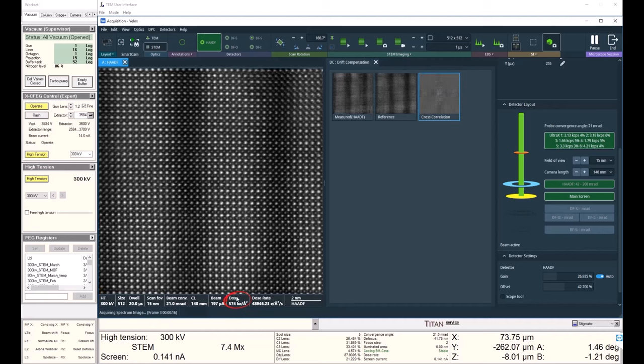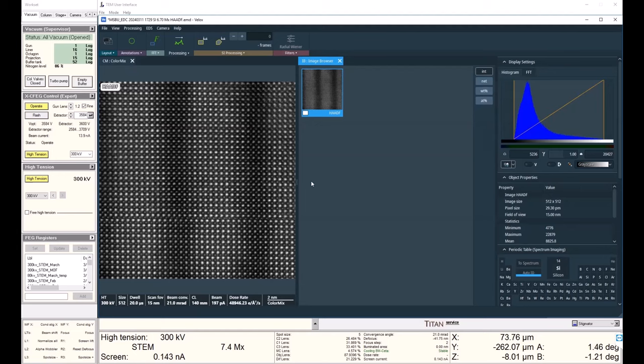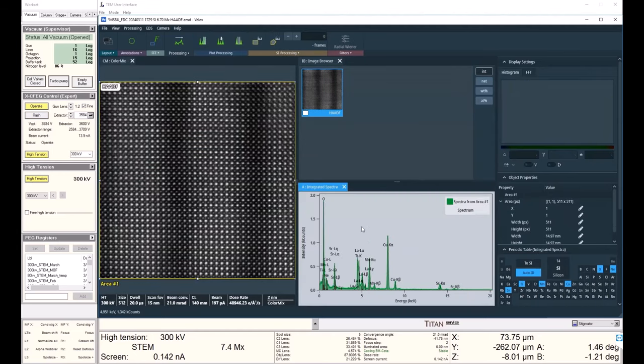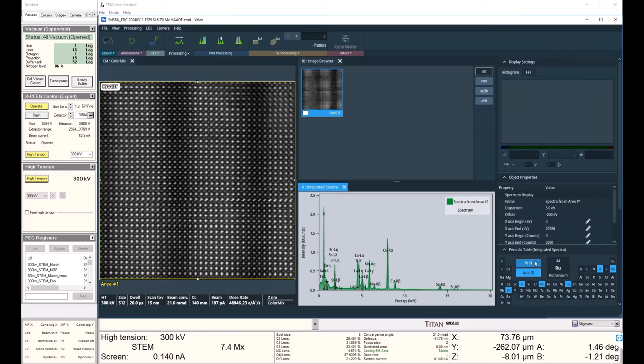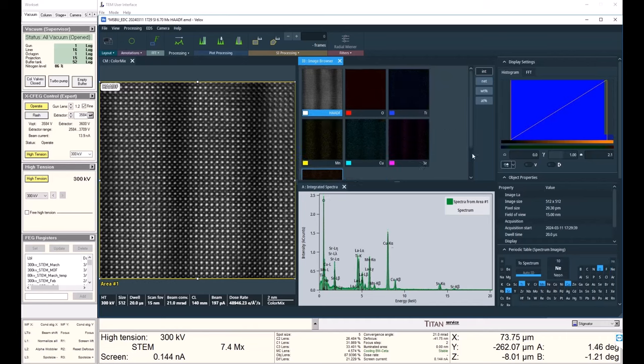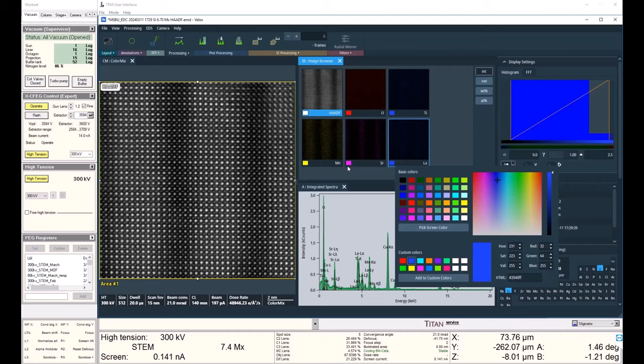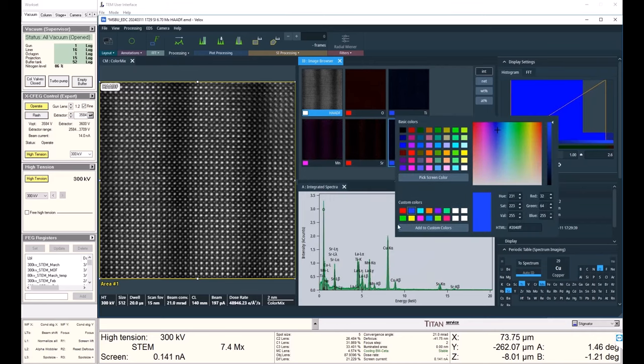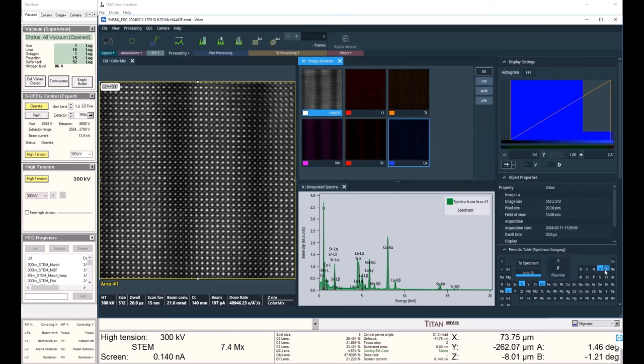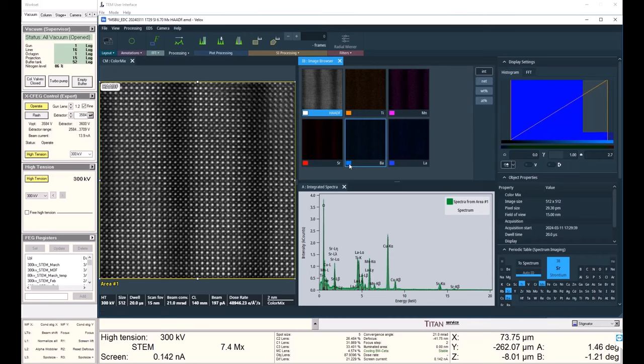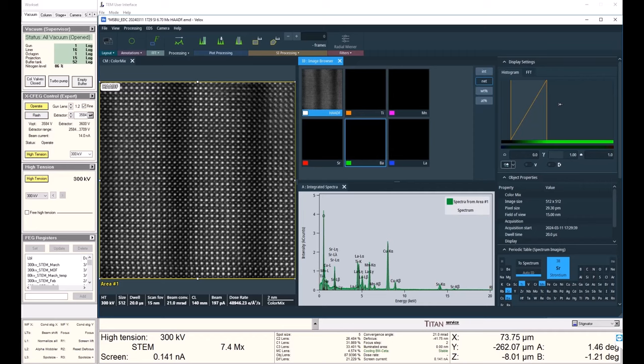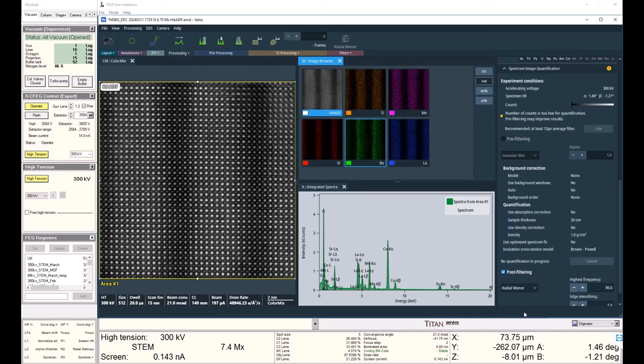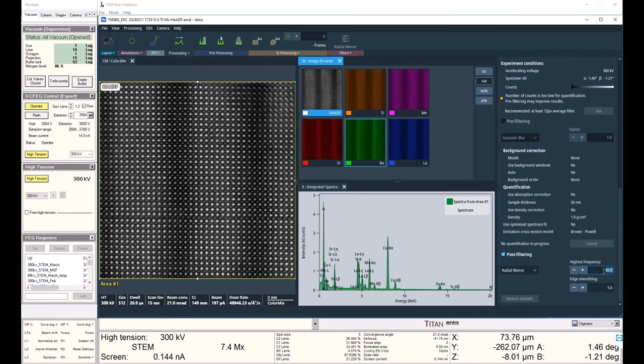I can take a look at my EDS map as I acquire. So I'll put down a spectrum image box and I can send my elements to the spectrum image. Get rid of any spurious ones, we don't need to look at copper, that's from the holder. And we can go ahead and set all of our custom colors as we wish them to be. Let's grab our barium as well. And go to the deconvoluted mode with the net option.